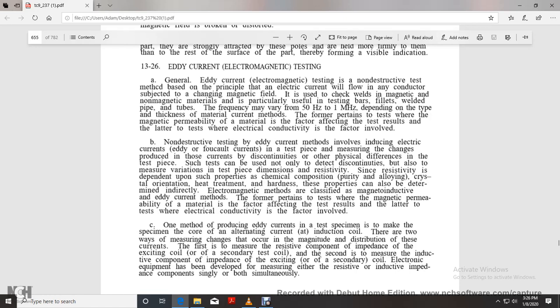The frequency may vary from 50 Hz to 1 MHz, depending on the type and thickness of the metal material. In the former method, the test pertains to magnetic permeability of the material as a factor affecting the test result; in the latter, electrical conductivity is the factor involved. In the eddy current method of non-destructive testing, electrical eddy currents are induced in the test piece, and the changes produced in these currents are measured to indicate discontinuities and other physical differences in the test piece.